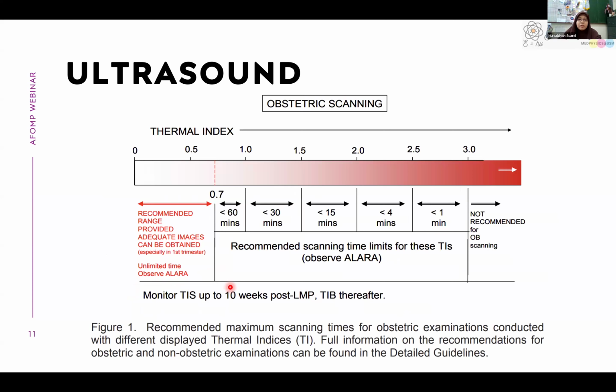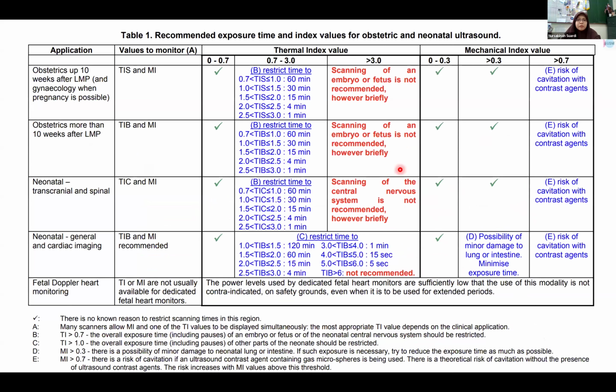This is obstetric scanning, where we can see the thermal index. If the thermal index increases, we encourage you to have less and less exposure, and if it is above 3.0, it is not recommended in OB scanning. So you can check the setting on the ultrasound. And this is another recommended table. You can see there is a TIS. We have a different thermal index for soft tissue, for bone, and for cranial, because different structures or anatomies would have different thermal effects. If it is below 0.7, we could consider that there is no limit on how long you do the imaging. But for the range from 0.7 to 3.0, for obstetrics, we have a suggested restriction of time, so that you won't have thermal effects on the fetus.